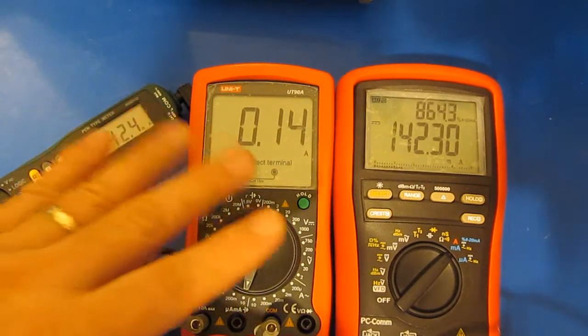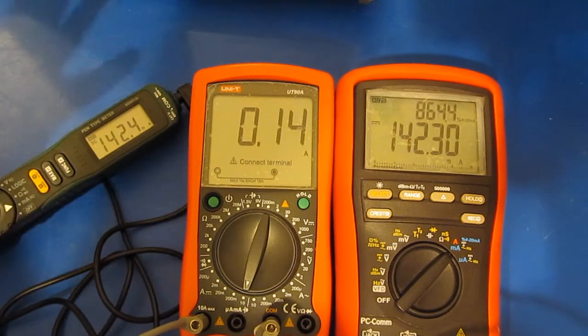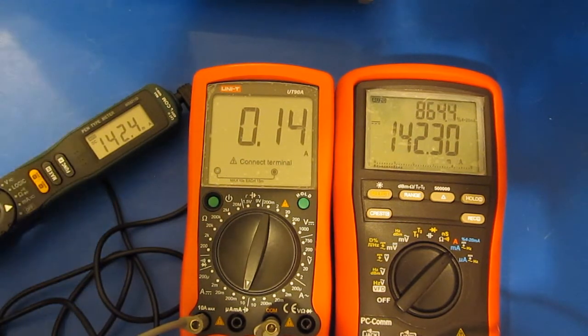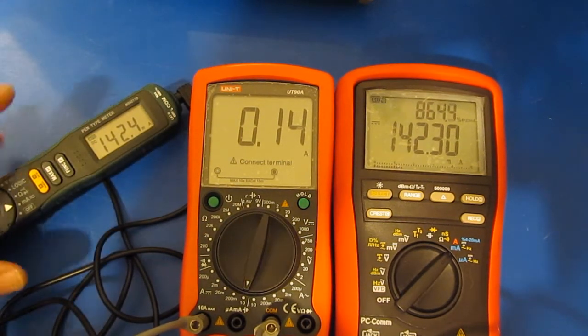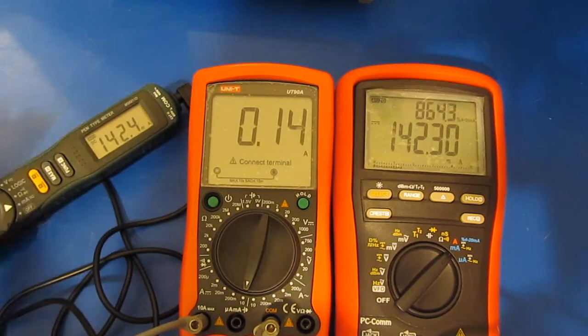But again at least for me typically what I'm doing when I'm measuring current is I'm using a clamp. Or I'm going to be using some type of a shunt. So the burden voltage of the meters really doesn't come into play very often.